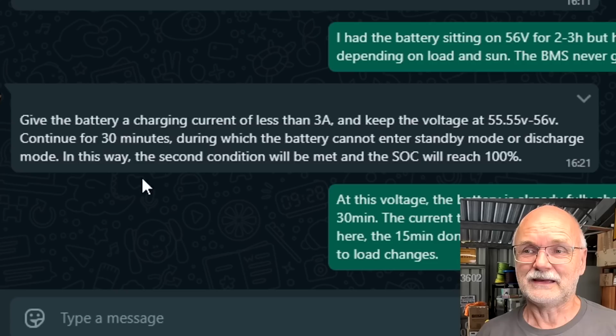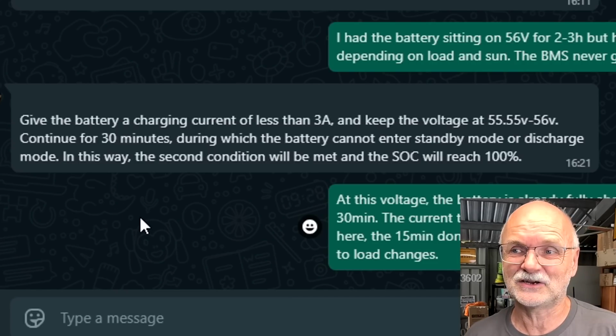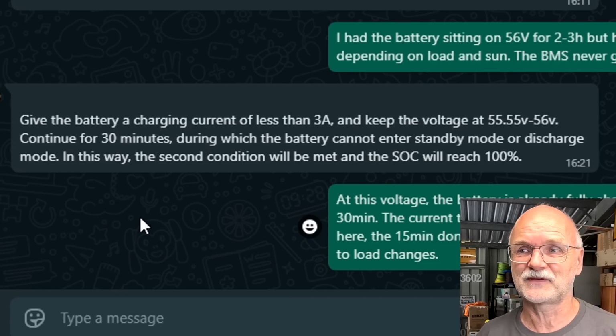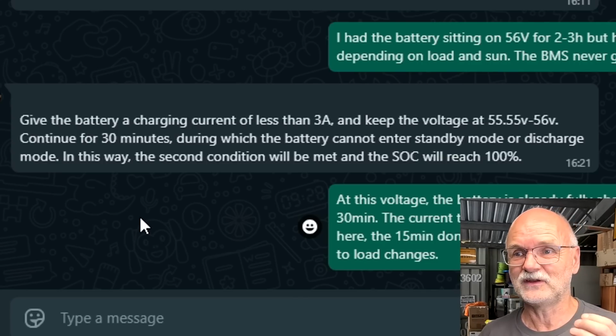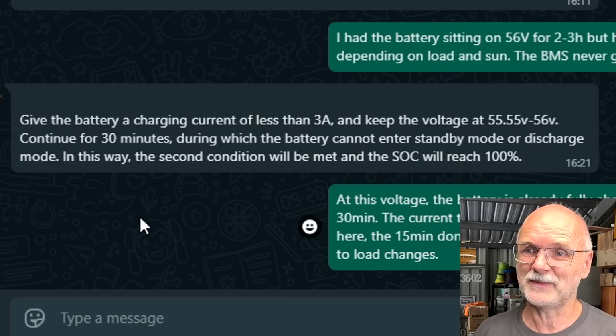And this is what you have: if you have reached your requested charge voltage of your battery and the current goes basically to 0, yet you have load and solar connected, there's always a bit of current going in and out of the battery, 1 amp, 2 amps in, then it discharges the battery again. So it always hovers around this point you have set. Seplos said, give the battery a charge current of less than 3 amps and keep the voltage at 55.55 to 56 volts, continuing for 30 minutes.